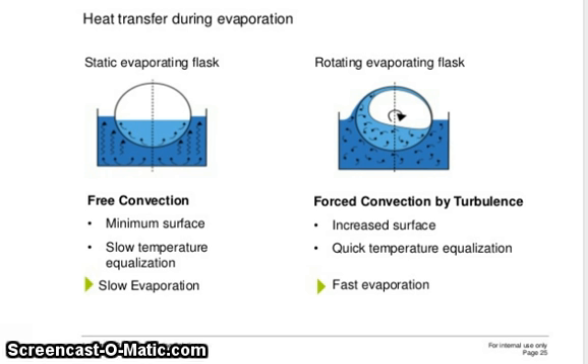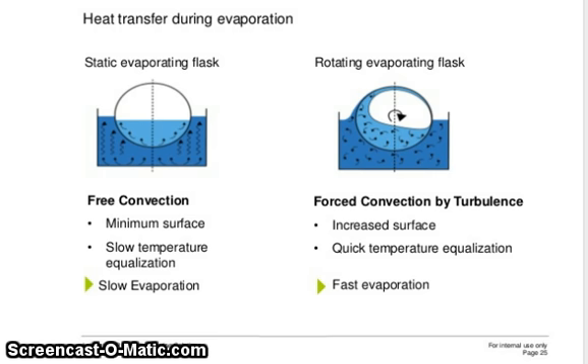Heat transfer during evaporation — static evaporating flask versus rotating flask. With a static flask, free convection occurs with minimum surface area and slow temperature equalization, resulting in slow evaporation. With a rotating flask, forced convection by turbulence gives increased surface area, quick temperature equalization, and fast evaporation.